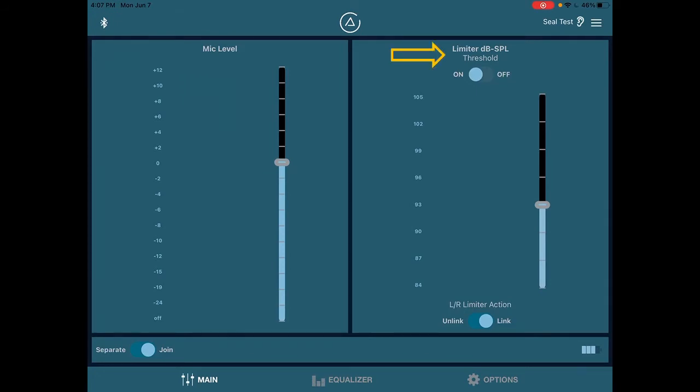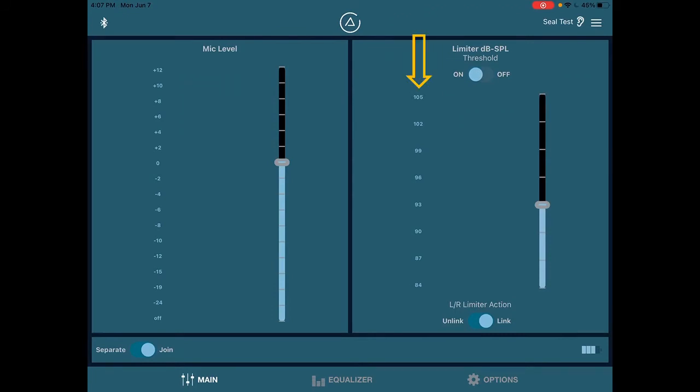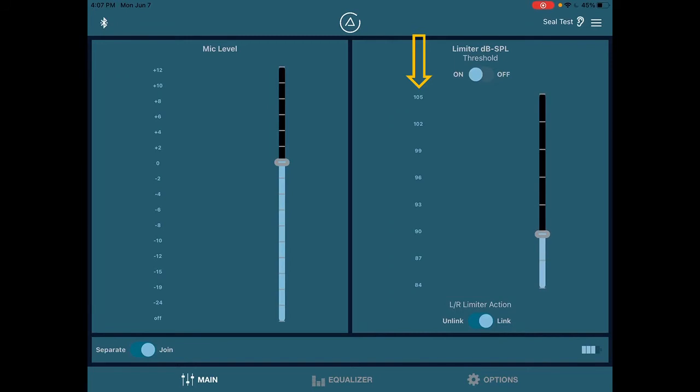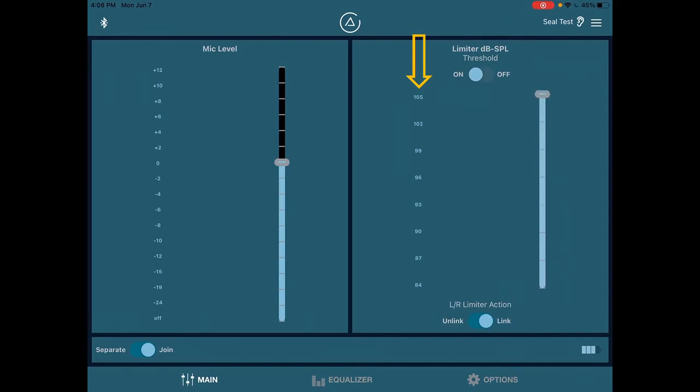To the right hand side, we have a limiter in dB SPL. Right now it's on. It can be turned off if you'd like to have it off. I'm going to leave it on because I love safety. So on this limiter, there are numbers to the left hand side. Those are dB SPL values. Say you're someone who would rather leave the mics at zero. That's fine. And yet you want to be protected against high intensity sounds. You can set the limiter to 90, 93, whatever works for you. Meaning you should have an idea of your sound levels and your length of exposure. And perhaps through knowledge you've acquired or making a decision with your audiologist or me, we can decide what might be safe for you with the limiter. And that can be set and can be left.